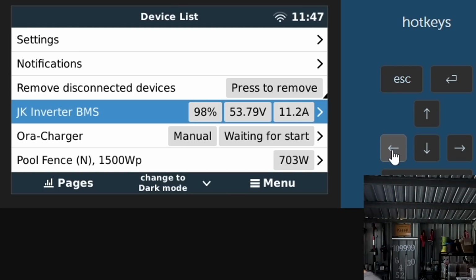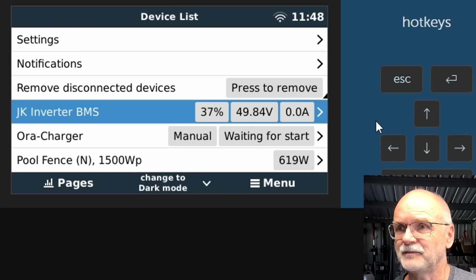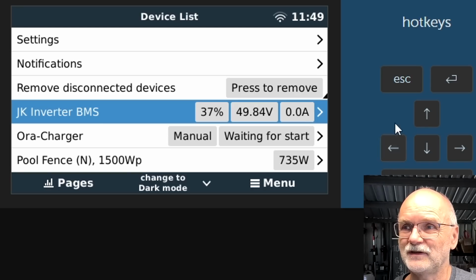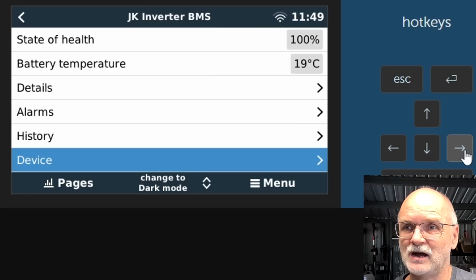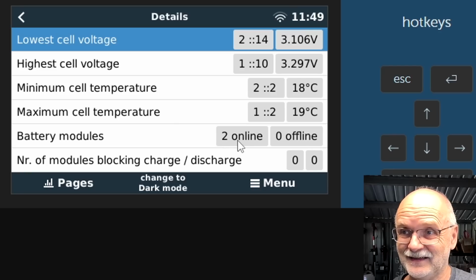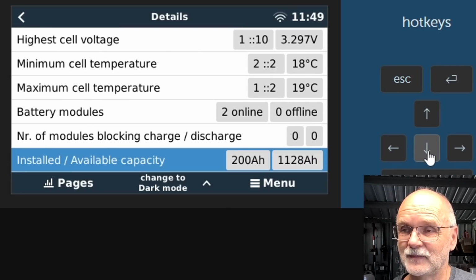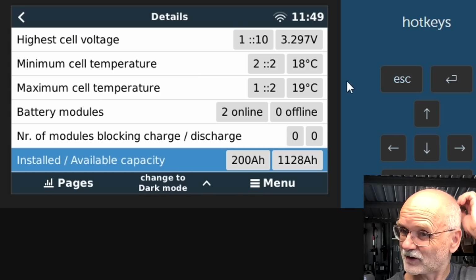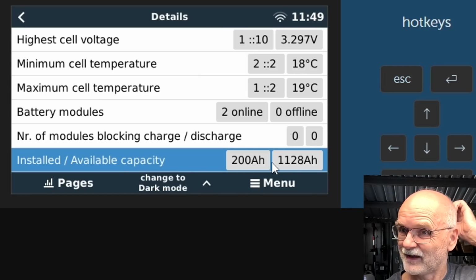I've connected the master Pace BMS now to the Cerbo. It shows us 37% state of charge. Let's have a look in details if it actually shows both batteries. It does show us both batteries, but the installed capacity is totally wrong and the available capacity is totally wrong again.